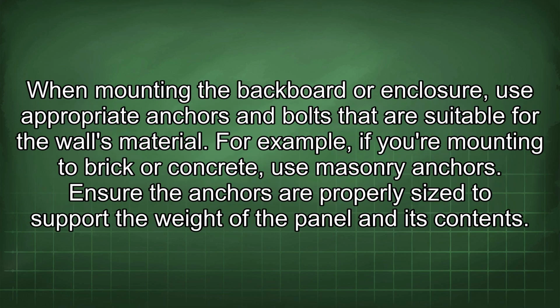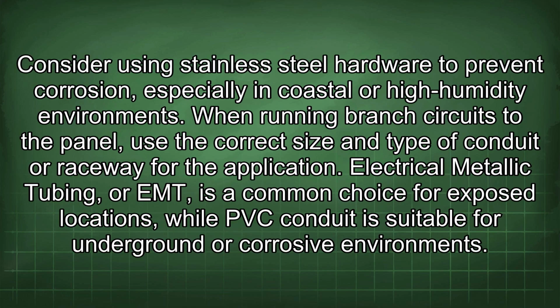When mounting the backboard or enclosure, use appropriate anchors and bolts that are suitable for the wall's material. For example, if you're mounting to brick or concrete, use masonry anchors. Ensure the anchors are properly sized to support the weight of the panel and its contents. Consider using stainless steel hardware to prevent corrosion, especially in coastal or high humidity environments.